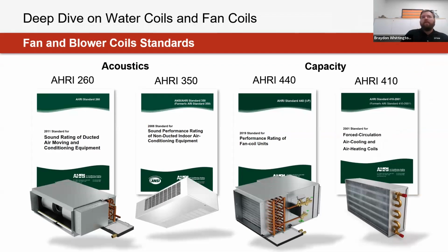We mentioned earlier, and there's a comment of, well, maybe how much space do I need for a water coil when maybe looking at an extension when looking at equipment, such as a fan coil or a single duct. Well, with fan coil specifically, they also have their own rating program through AHRI for the fan coil unit's performance as a whole. So it's actually testing that water coil with the fan coil. So it's taking into account any concerns that you might see, especially for close coupling or having that fan position close to the coil itself. And from an acoustics perspective, or how much noise is going to be emitted from this product, there is also some testing for both ducted, as per AHRI 260, and unducted applications, or AHRI 350, for these products, just because, as we'll see here in a little bit, it's common to configure these in both of these applications.